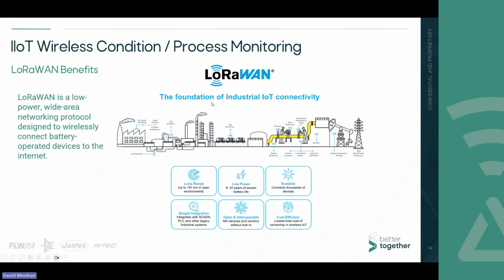I want a gateway maybe in the middle, or on the left side, or the right side, and I want all of these sensors to communicate to the one that's in closest proximity and has the highest signal strength. That's why I like LoRaWAN. A typical plant using wireless HART or a mesh network might require 15 to 20 gateways, but we can accomplish the same measurements with 3 or 4 utilizing LoRaWAN.